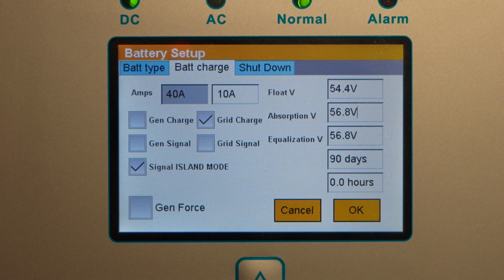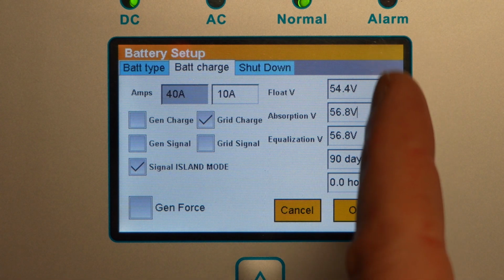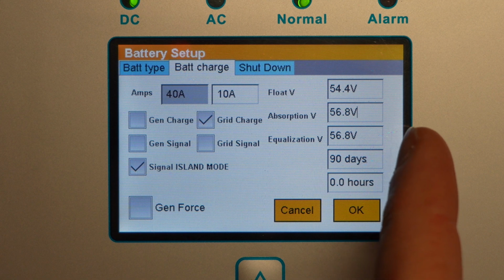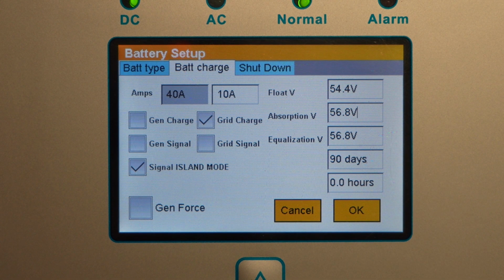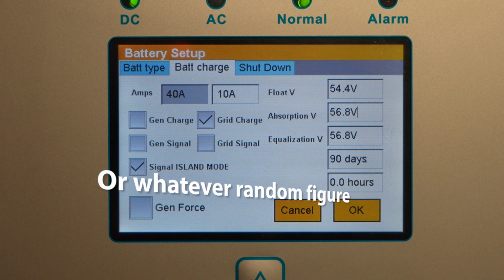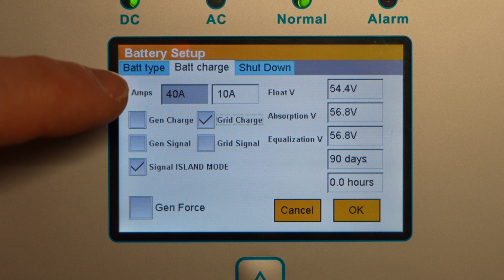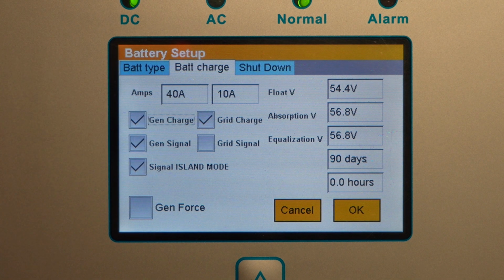The next page, the battery charge. Once you're connected to a lithium BMS, this page is largely irrelevant. None of this has any effect. The float voltage, absorption voltage, or equalization voltage, none of it will affect the BMS. Equally, neither will the 10 amps on the charge. We can get it to unhighlight by unticking grid charge or highlight. Now the 40 amps set there for the generator charge, get it to highlight if I like. I don't know whether that has an effect on charging the battery. I doubt it, if none of the rest of it does, but I haven't tried it on the generator, so I can't tell you that.